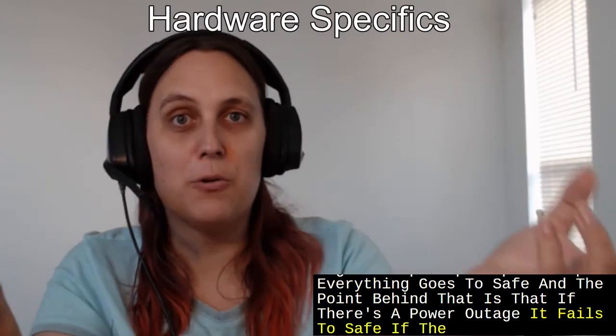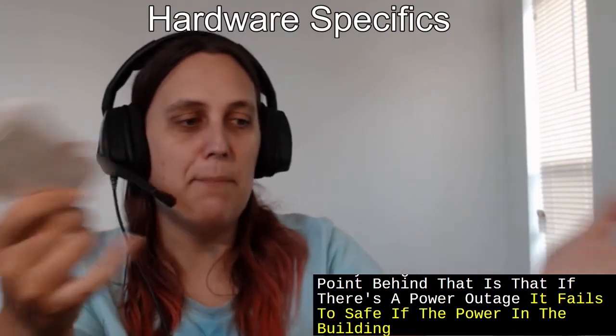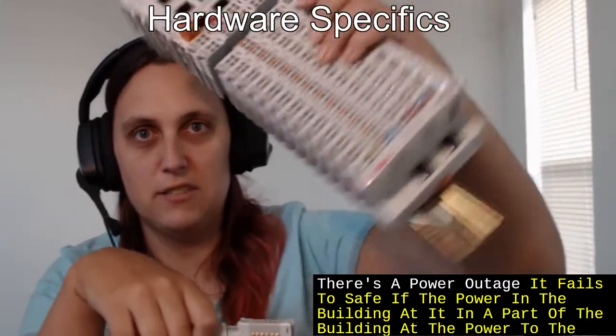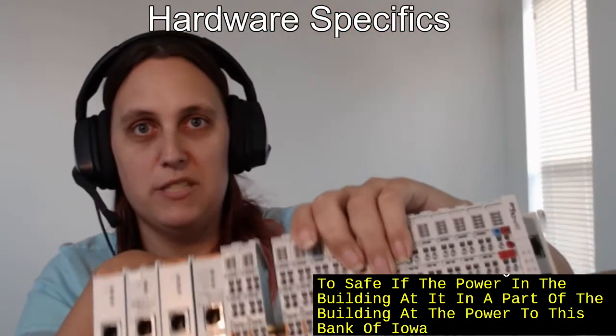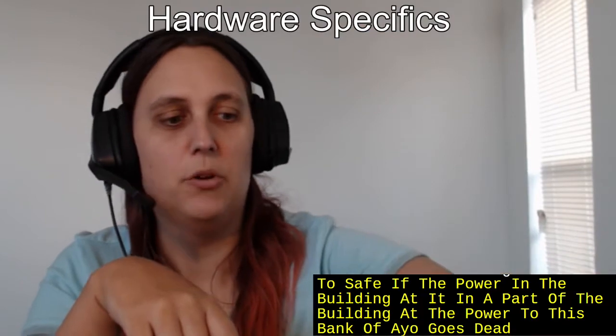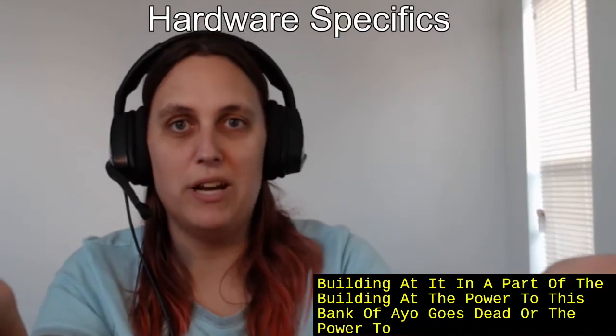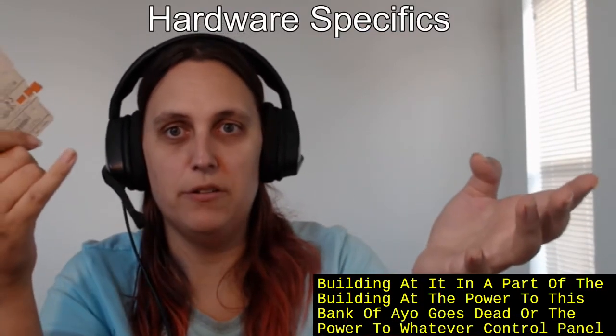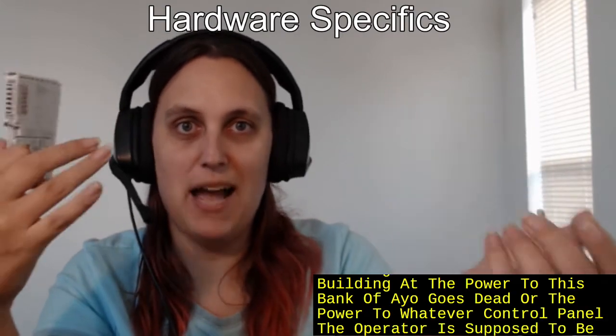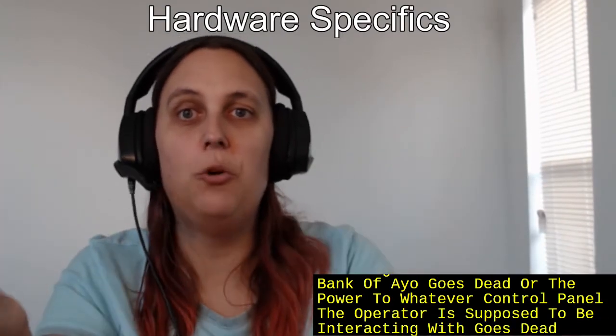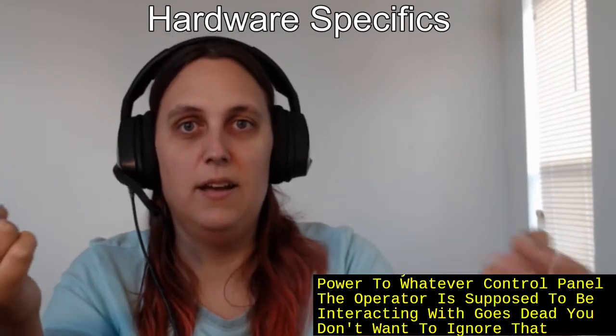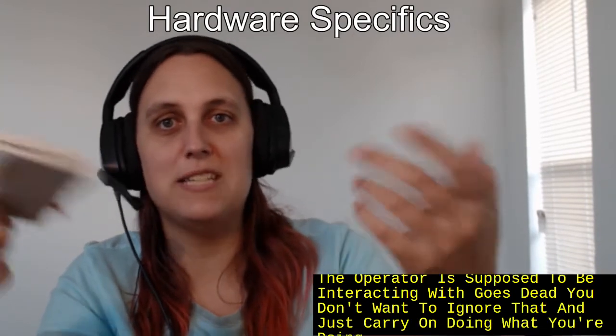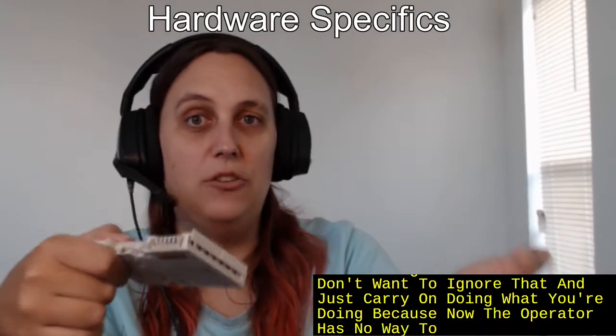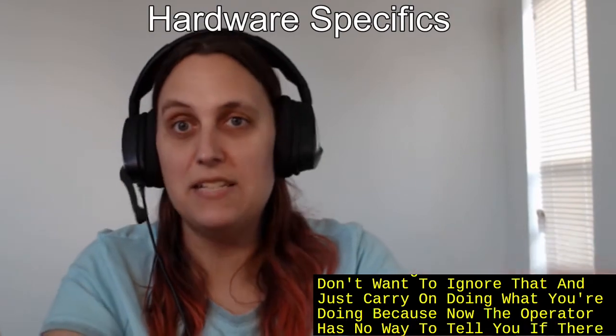If the power in a part of the building, or the power to this bank of IO goes dead, or the power to whatever control panel the operator is supposed to be interacting with goes dead, you don't want to ignore that and just carry on doing what you're doing, because now the operator has no way to tell you if there is an actual problem, right?